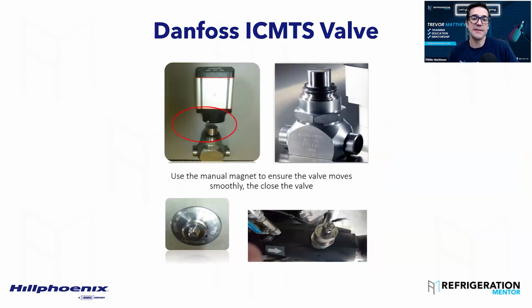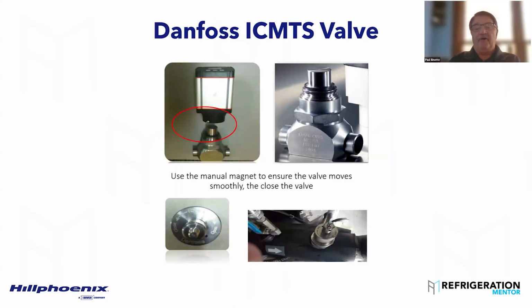So fantastic. Yes, sir. So part of the startup procedures is verifying your valves. On our new Flex 2.0s, we're utilizing CCMT valves, which look more like a Danfoss CCM valve. We still have racks that utilize the ICMTS valve. It's a fantastic valve. It'll work off a 0 to 10 signal. You can manually manipulate it off a magnet, which is down that bottom left corner and bottom right corner, or you can put the controller in manual if you lose your signal or you're outboard, and actually run the rack that way.